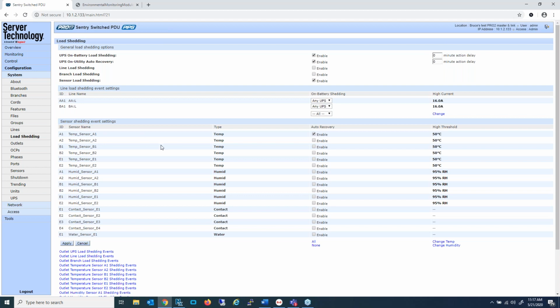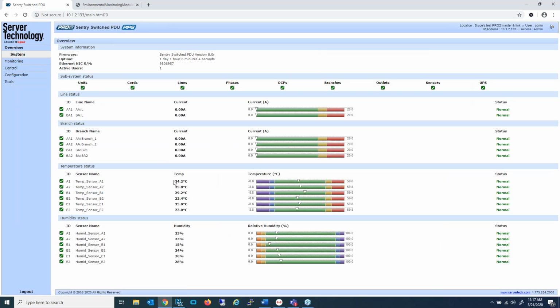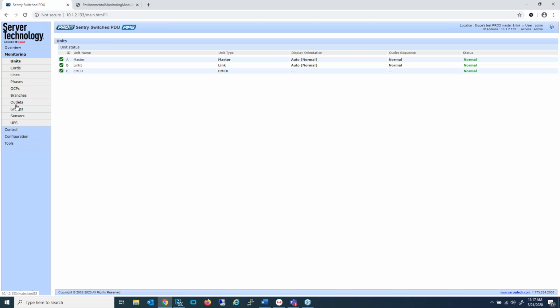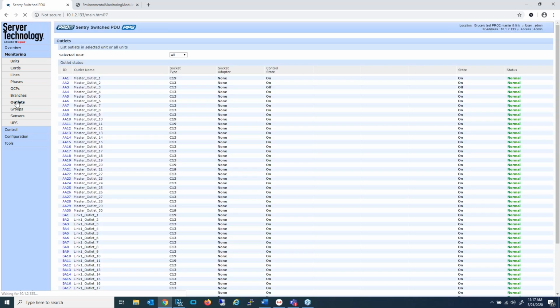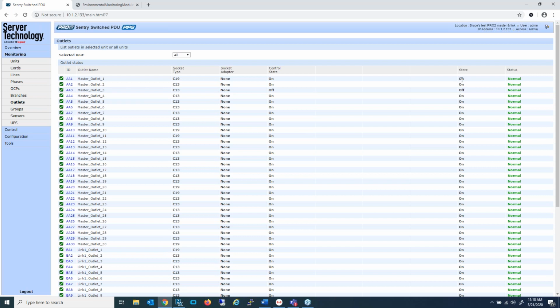So let's take a look at actually making a load shedding event occur. I don't have a good way to reach out and heat up the sensor, so I'm going to be a little bit tricky. I'm going to start by going to the overview page and taking a look at the current temperature as measured by sensor number 1. Temperature is 24.2 degrees Celsius. Let's take a quick look at outlet status. Outlet number 1 and 2 are presently on. Outlet number 3 is presently off.